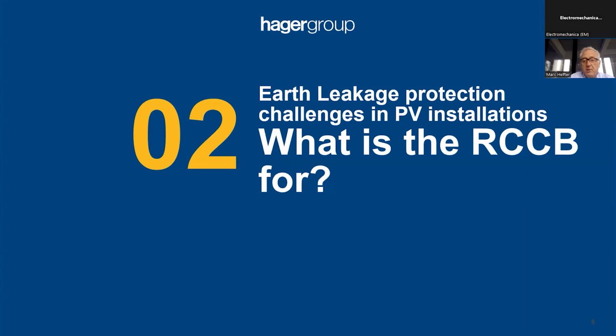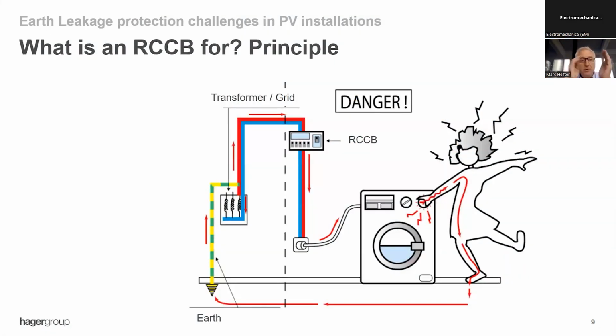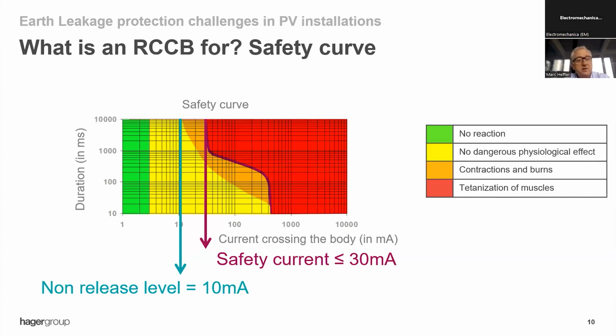This is maybe a reminder for you. Why do we put RCCBs in electrical installations? It's to protect people, not to protect the goods or the building. It's to protect people against the danger of electricity. When somebody gets in touch with an electrical conductor, there is a current going through his body, going through the earth, and the RCCB detects this current going through the body. If it's higher than 30 milliamps, the RCCB trips to protect the person.